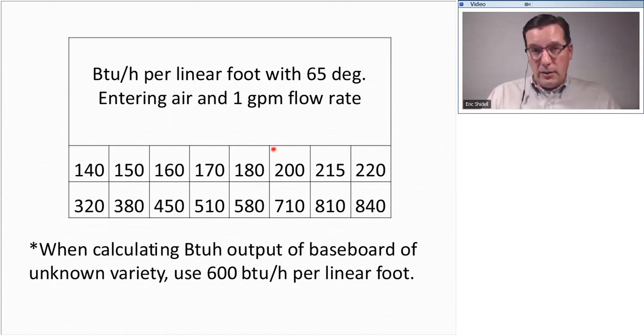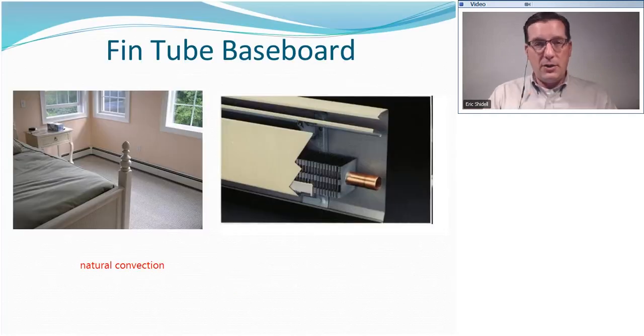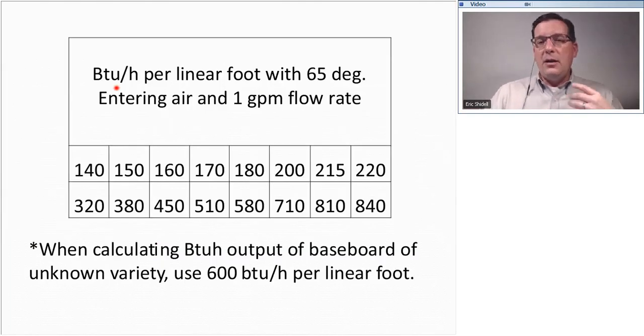So if you need to calculate the BTU output of baseboard of an unknown variety and you don't have this handy dandy factory chart, use this rule of thumb: 600 BTU per linear foot. Now this can come in handy in a couple of ways. For example, you're called out to a house because Johnny's room, the children's bedroom or whatever, isn't as warm as the rest of the house. And you identify that the boiler is operating correctly, the rest of everything is operating correctly. You verify that the shrouds are not bent or broken, that the damper is open, there's nothing blocking the baseboard, it's not got dog fur underneath it, it's all clean. Yet that room still is underperforming.